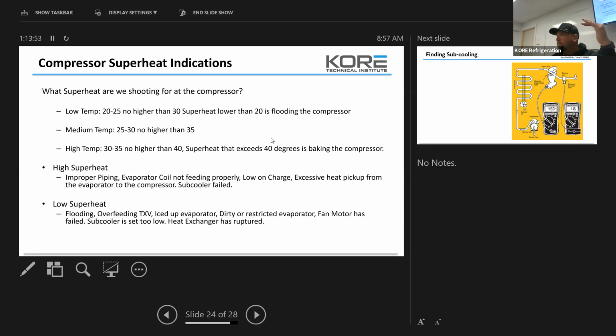If you overheat a compressor, internal damage has happened. As soon as you start to cool it back down and it starts to pump properly, it might work while you're there. But a lot of times, I'm not even going to give a percentage, I would end up going back and changing the compressor in a couple of days because it went down again. Would it help to do an amp draw at all or no? It just doesn't show up when you're there. It can run and cycle on and off, but without fail, the next day or a couple hours or days later, the valve plate fails and the valves bust or something goes wrong.